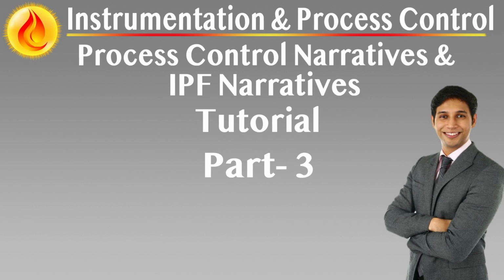Alarm settings are not included in the narrative but are stored in the project instrument database, e.g., in tools, for centralized management. Summary. These additional requirements define how the IPF operates in real-world scenarios beyond the basic trip logic. They are critical for ensuring that safety functions are not only logically correct, but also practical, testable, maintainable, and aligned with plant operations. Including this information in the IPF narrative allows for reliable implementation, effective operations, and compliance with safety lifecycle standards.